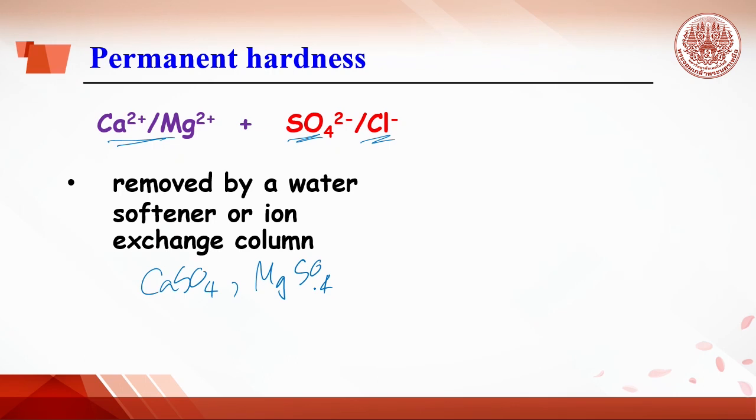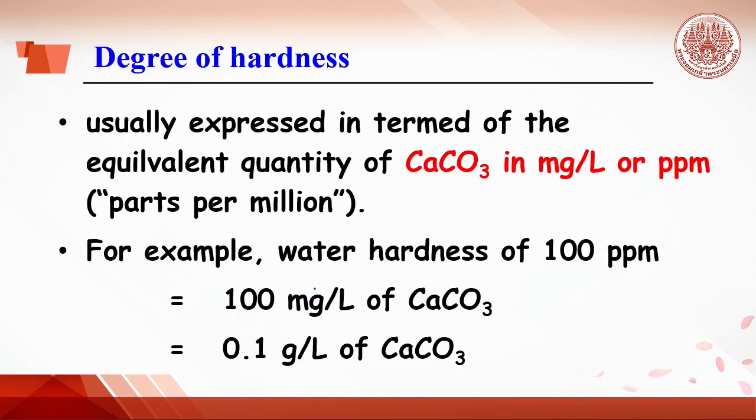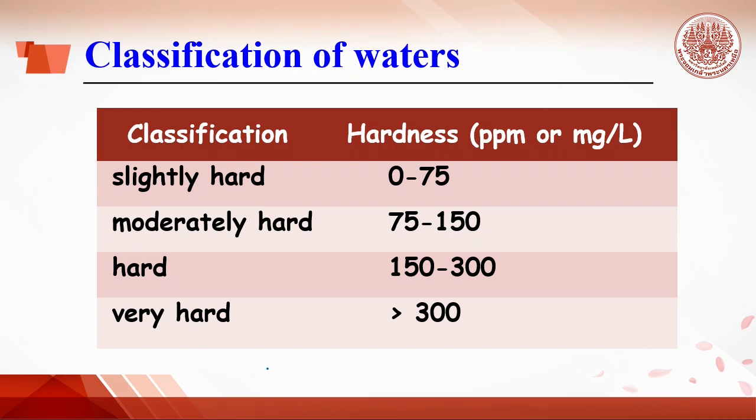It can be removed using a water softener or ion exchange column. Hardness of water is usually expressed in terms of equivalent quantity of calcium carbonate in milligram per liter or ppm, which stands for parts per million. For example, water hardness of 100 ppm means 100 milligrams per liter of calcium carbonate or 0.1 grams per liter of calcium carbonate in water. Here is the general guideline for classification of water. For example, water with hardness of 0 to 75 ppm is defined as slightly hard.